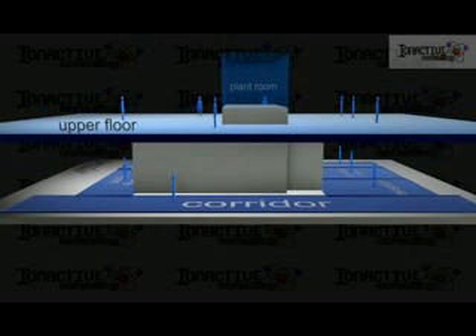In this model, the bunker is surrounded on all sides by areas of public access, including consulting rooms, plant rooms, and a control room. The shielding design is optimized so that work in these areas can take place unhindered. In some cases, the designed shielding performance will be partly based on occupancy levels — for example, restricted access to the plant room may allow less shielding to be used.